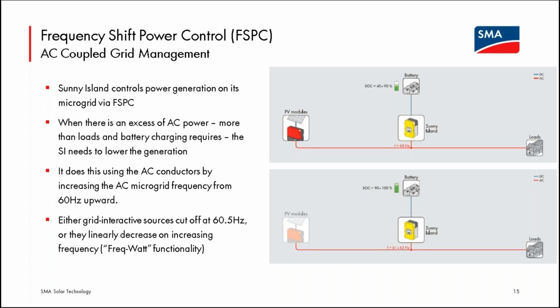And now even in the United States, there are large areas where utilities require grid-connected PV inverters to be able to respond to FSPC that is actually implemented by the utility. If that utility grid frequency goes up, the inverters need to respond by throttling down their active power. This may be called freq-watt, for frequency and power watts. So SMA inverters can do this. Now more and more grid-tied inverters have this capability, whether or not it's enabled. And so it's a very effective way to throttle excess power down.